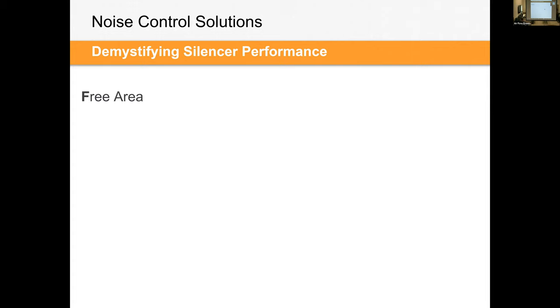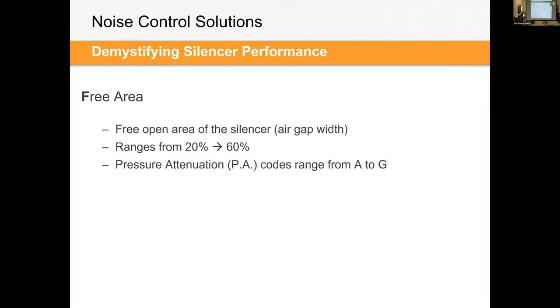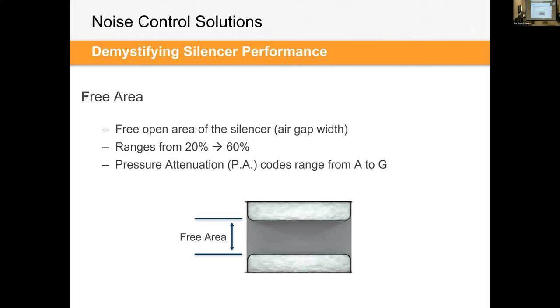So free area is a common consideration with silencers and extremely adjustable on all of our Price silencers. Basically it is the free open area or the air gap width on a silencer. This air gap width, or the opening of the baffles, will range from about 20% to 60% on any silencer. This is what I'm talking about here. You have baffles typically on the side, and then this open free area in the middle where the air is going to transmit through. That area can be adjusted. The tighter the gap, the smaller the free area, the bigger the baffle, the more insertion loss you're going to get, but you're also constricting that airflow quite substantially. The wider the gap, the smaller the baffle, the less the pressure drop, but the less the insertion loss.